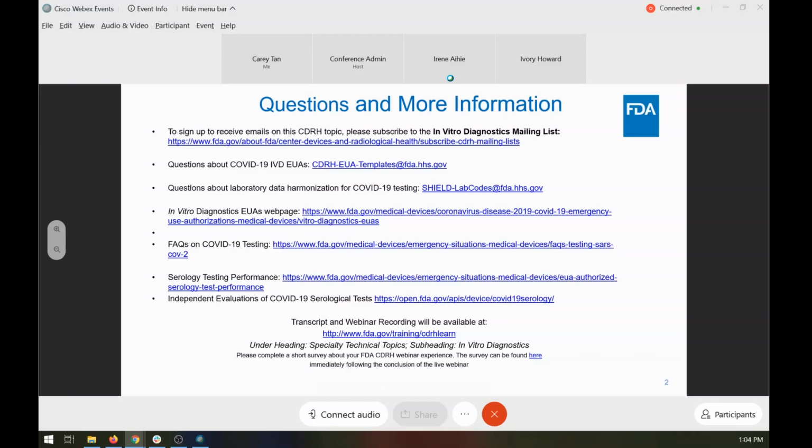Yeah, thank you. I would just like to echo Toby's point. It's somewhat governed by the extent to which your labeling specifies those reagents. And I know we've seen some small changes to extraction buffers, perhaps removing certain components due to shortages. And I think that really needs to be looked at by a subject matter expert rather than just providing a blanket policy, because certainly small changes in pH or the composition of a buffer versus taking away carrier RNA, for instance, are two very different changes that may need consideration by someone on the review team.